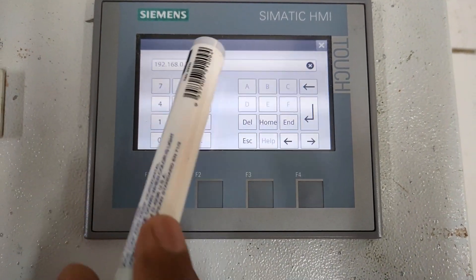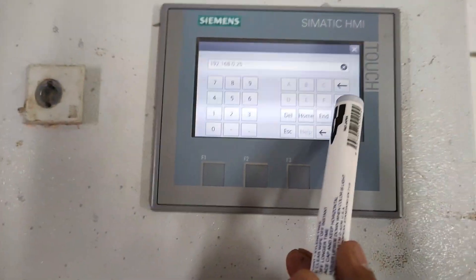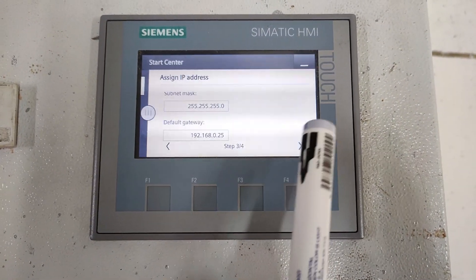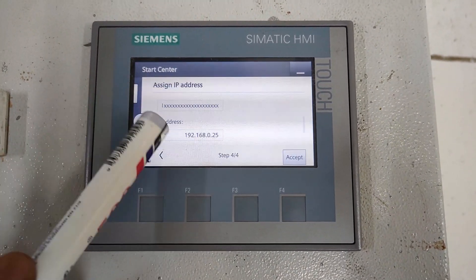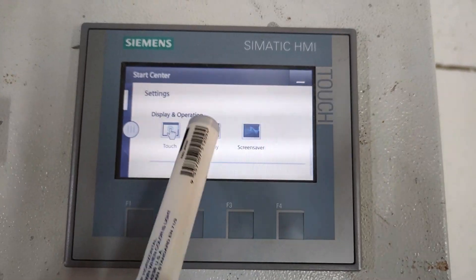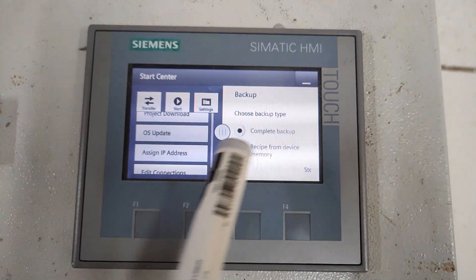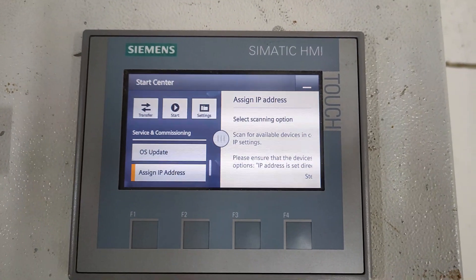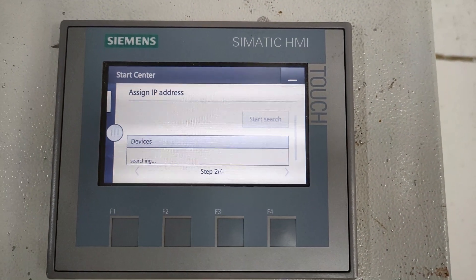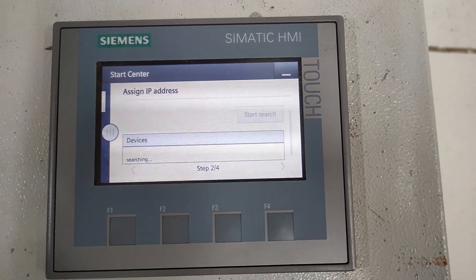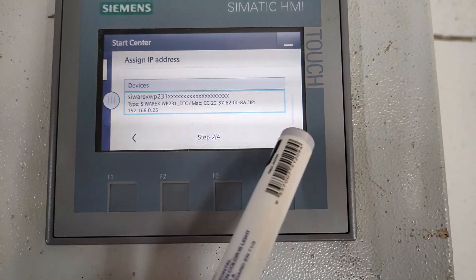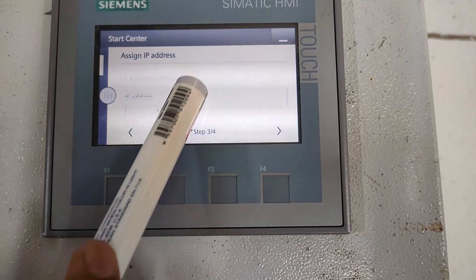You can enter your desired IP address. For testing purposes I am setting it to 192.168.0.25 — I will go back to 21 later. Select the station name, then assign the IP address. Now go back and scan accessible devices on the network. After scanning, it confirms the IP address is now 25. By this method you can set the IP address of any PLC or module.